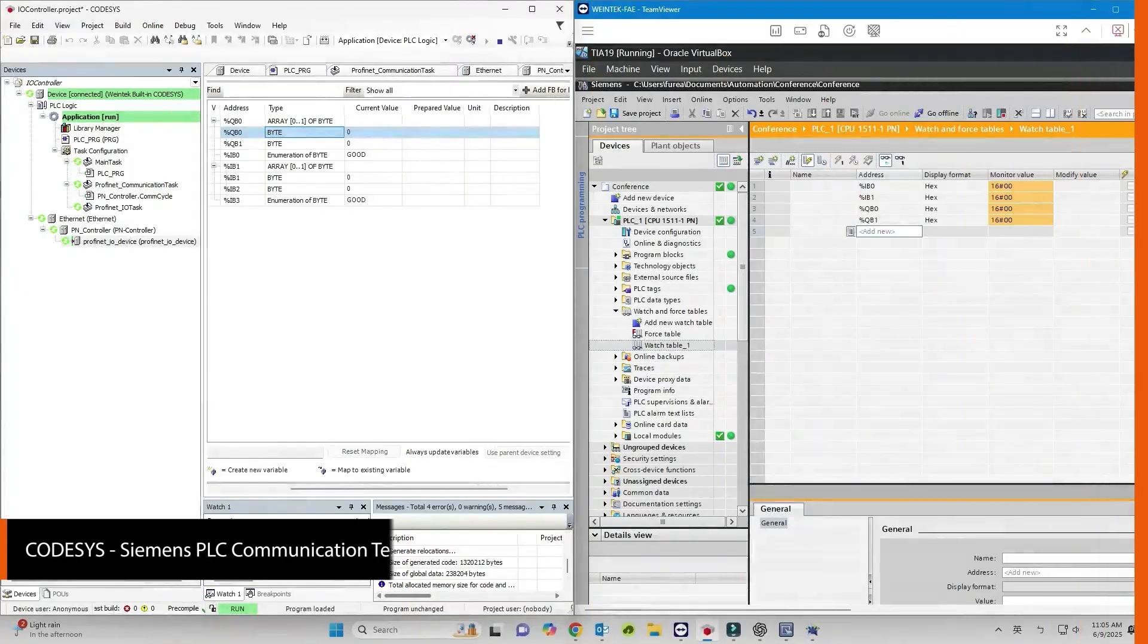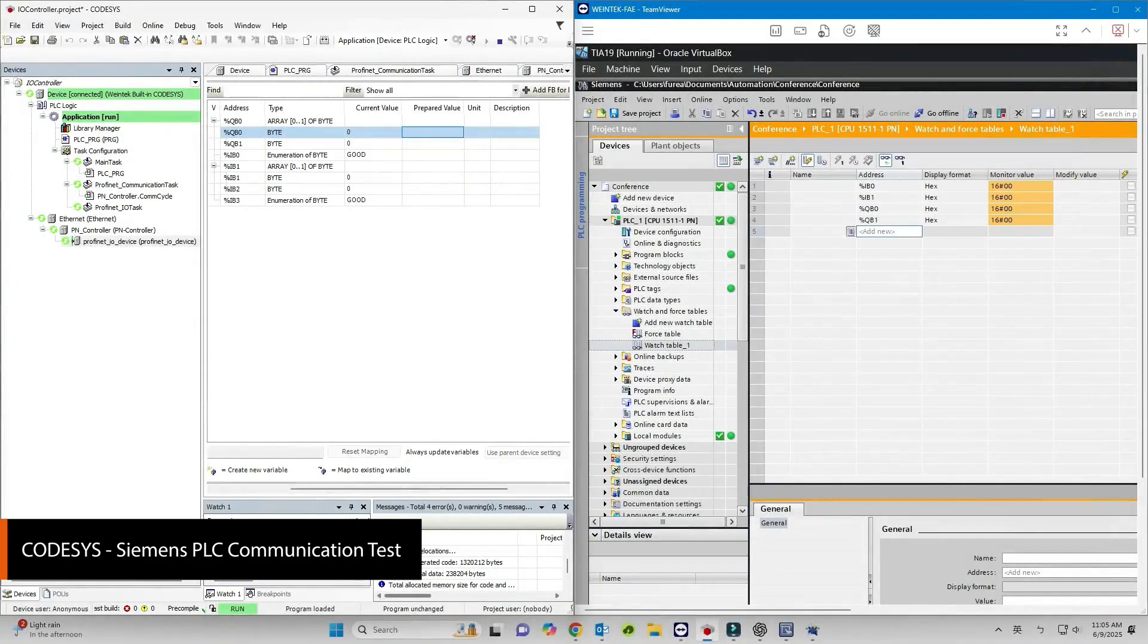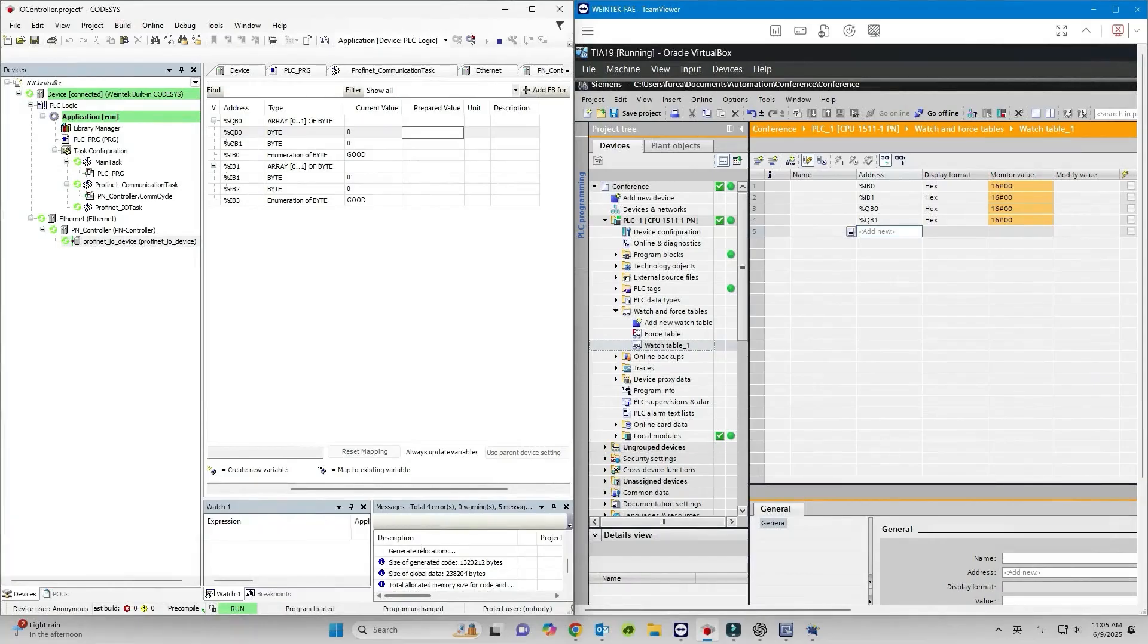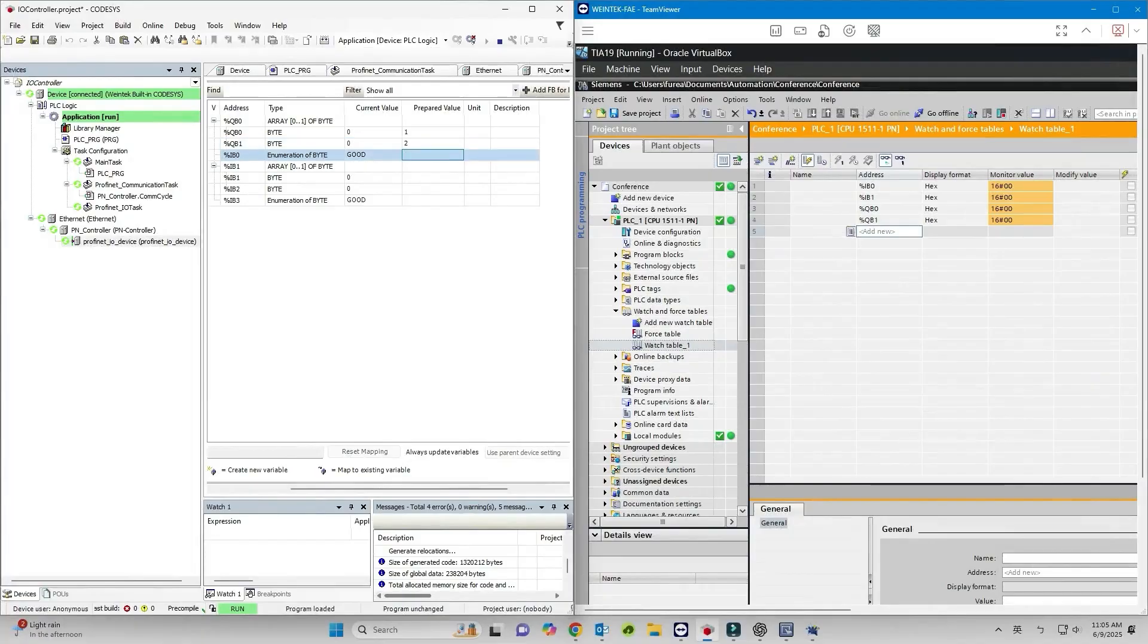Write values to QB0 and QB1 in CODESYS. If the values appear in IB0 and IB1 of the Siemens PLC, the communication is working.